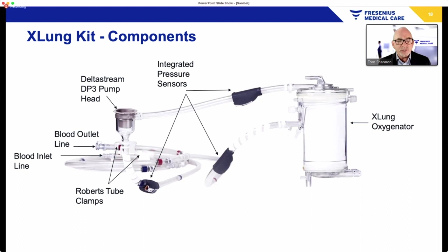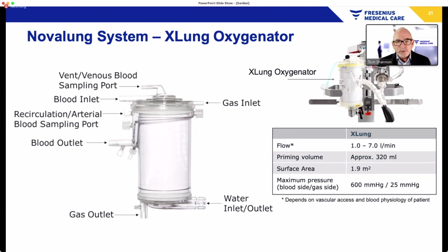If you're not familiar with the design of this original Mitos designed oxygenator, the blood comes in at the top. There's a low flow pressure area that's great for trapping bubbles. And you've got a 360-degree view around this oxygenator. You can see clots or bubbles if they're there. The blood travels down through a polyethylene heat exchanger, comes across the gas fibers, rises back up through the gas exchange fibers, and then down and out in the middle of the oxygenator.